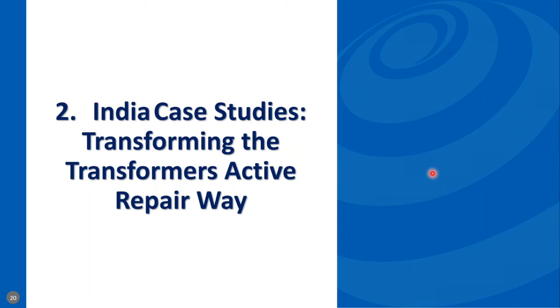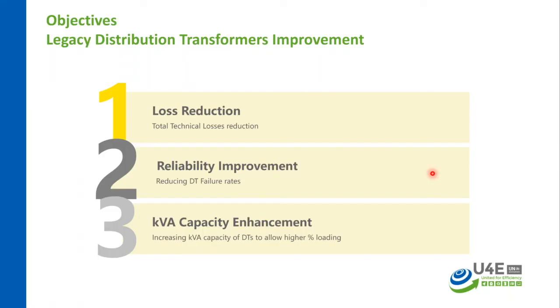Particularly, the replacement of the transformer is expensive on a return on investment basis, where the ROI for such projects, in terms of simple payback period, can be more than 8-10 years or even more in some cases, depending on the load factor of the system. So what the Indian utilities have started doing now is that instead of buying a new transformer, where there is a lot of hassle to convince the regulator and justify the ROI, they are trying to improve the performance of the existing inventory through active repair. And I will be very happy to share that case study with you.